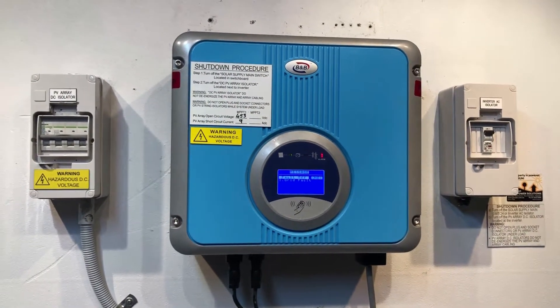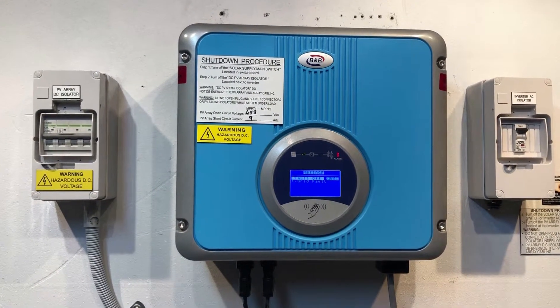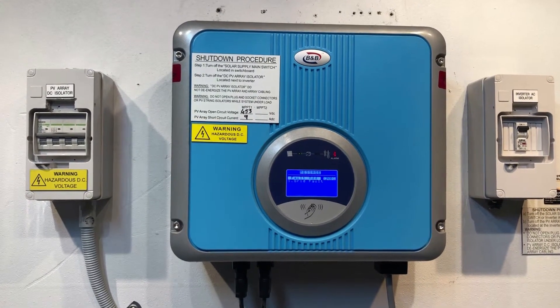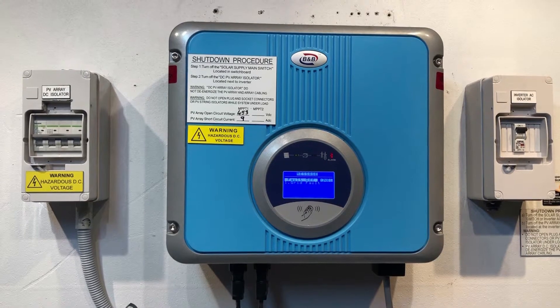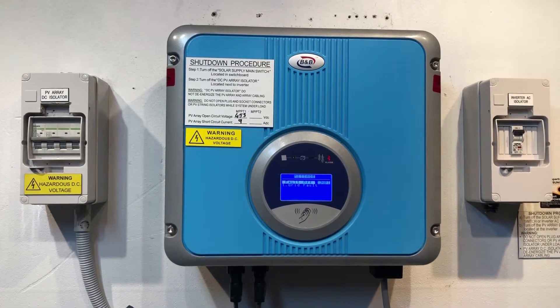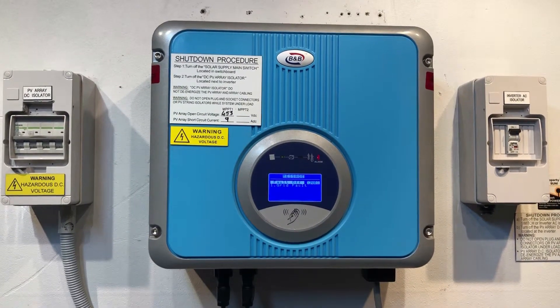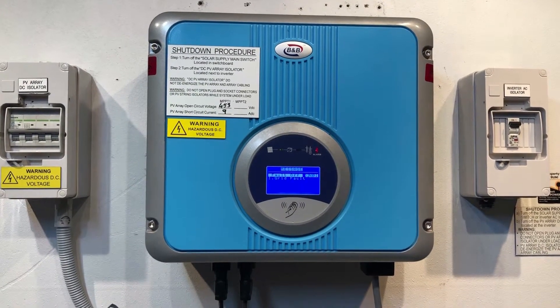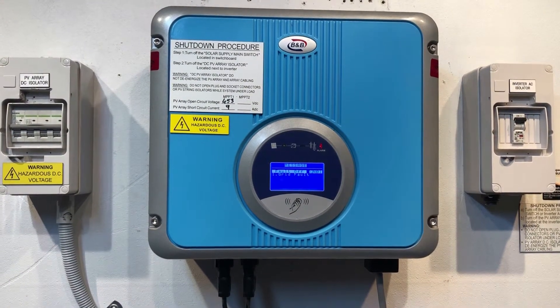In this case, this B&B inverter is not seeing any power from the electricity grid. Because of that, it's turned off and it's waiting for the grid to be reconnected so it can start operation again. So what we need to do is find out why it is showing a grid fault.